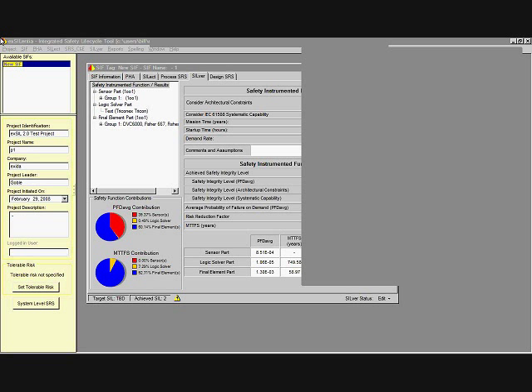Okay, we have another question. For what type of voting application should voting on groups be used instead of voting on legs in one group? In the exSILentia tool, I generally go with voting between groups because most of the time the components within one group are tested and repaired at the same frequency. If you have some special problems and you must test at a different frequency, then you can vote between groups and specify the products as different groups, and the exSILentia tool will work perfectly.